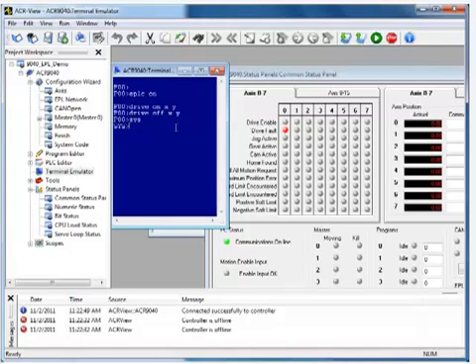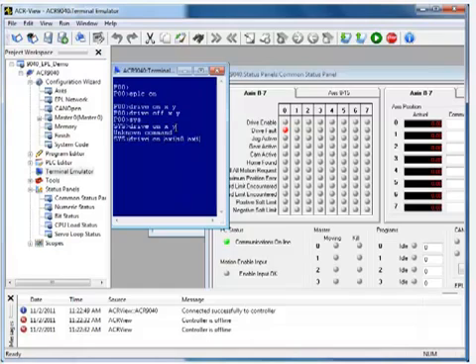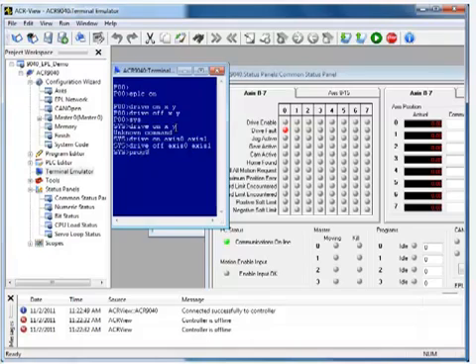From the SYS prompt, if I try to do DRIVE ON X Y, it'll say UNKNOWN COMMAND, because it doesn't recognize X or Y. But if I do DRIVE ON AXIS 0 AXIS 1, both will enable. Same thing with DRIVE OFF. Then I can go back into PROG 0 and back to the P00 prompt.